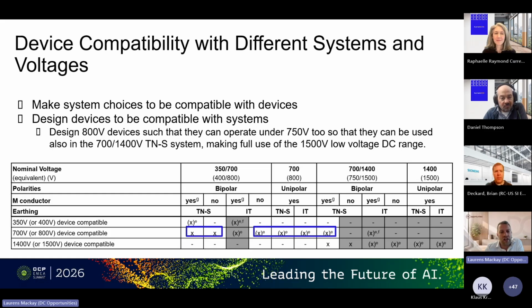If you're making 800 volt devices, you can operate them in the first two systems. If you want to operate them in the other four systems, you need to design them with extra clearance to earth. But for the last of these systems, you need to make sure you can operate under 750 volts as well.